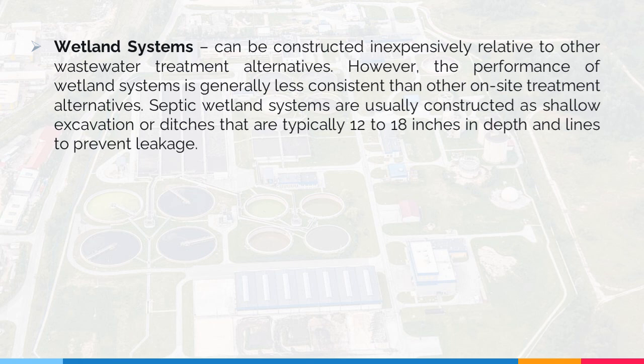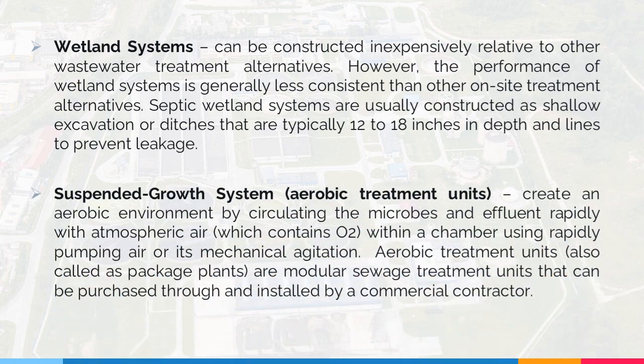Wetland systems can be constructed inexpensively relative to other wastewater treatment alternatives. However, the performance of wetland systems is generally less consistent than other on-site treatment alternatives. Septic wetland systems are usually constructed as shallow excavations or ditches, typically 12 to 18 inches in depth, and lined to prevent leakage. Suspended growth systems — aerobic treatment units — create an aerobic environment by circulating microbes and effluent rapidly with atmospheric air containing oxygen within a chamber, using rapidly pumping air or mechanical agitation. Aerobic treatment units, also called package plants, are modular sewage treatment units that can be purchased and installed by a commercial contractor.